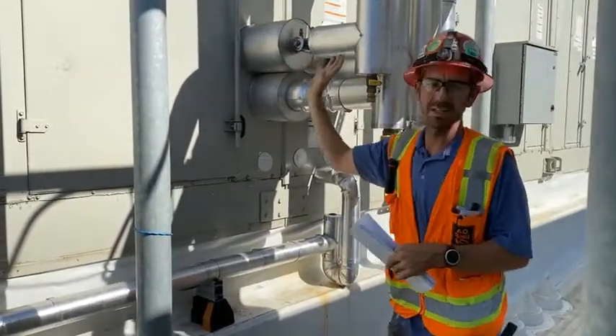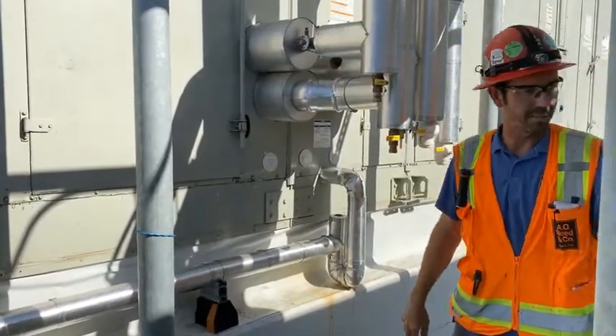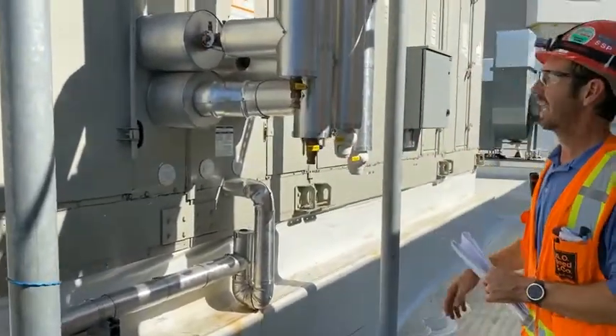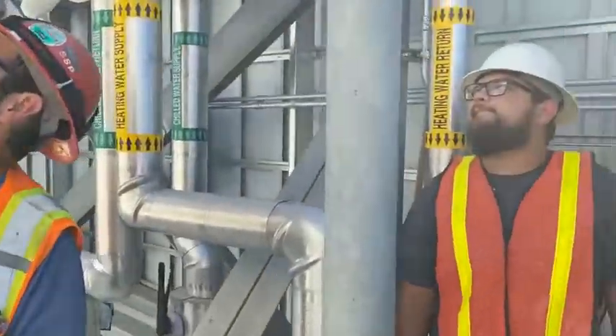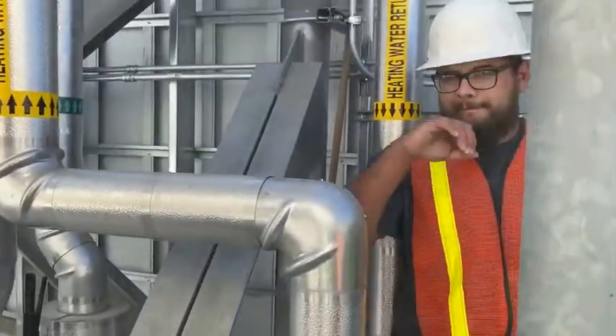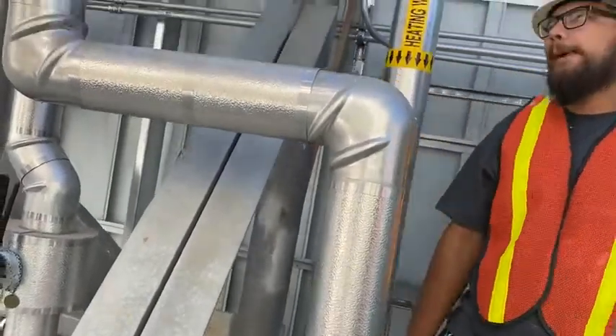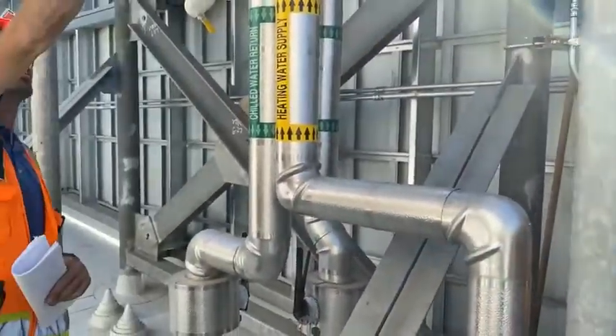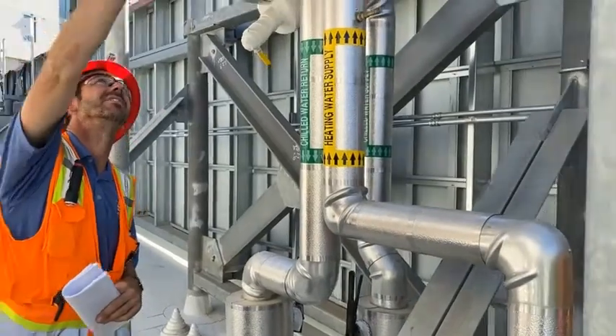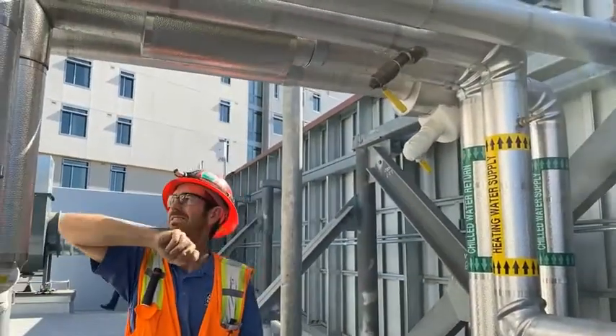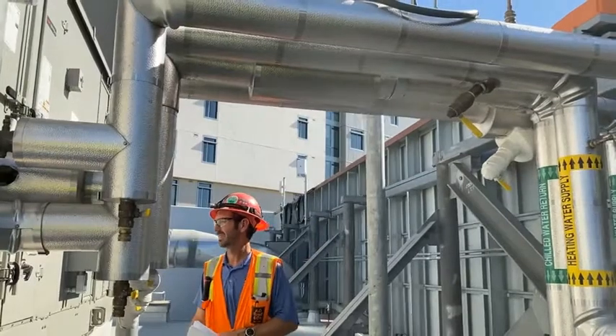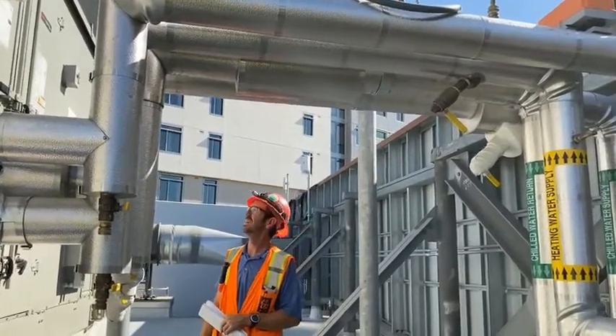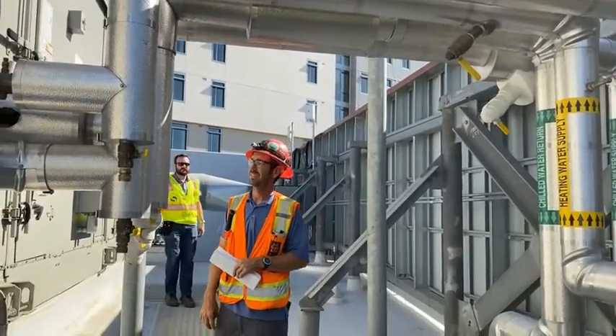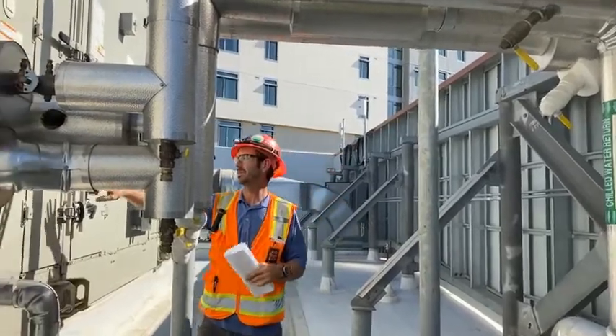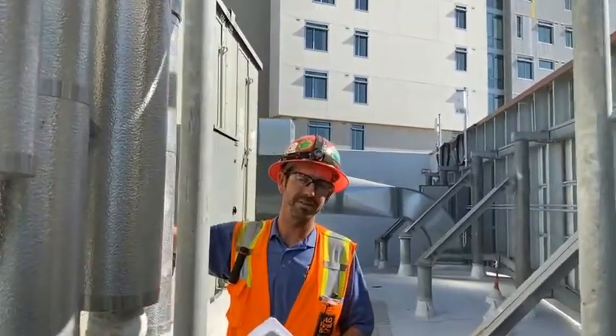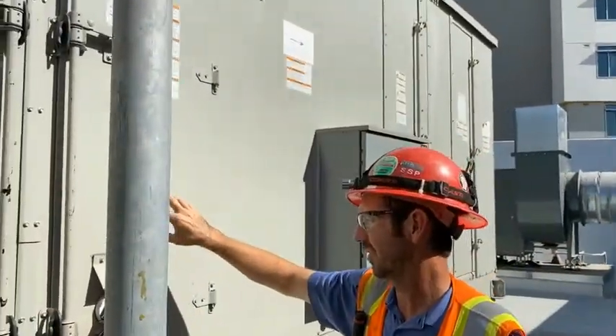So if we're isolating the unit, we'll just do it at the main shutoff valves that are right back behind us. If you do work, use the vents that are up at the top of the piping to vent out any air. Same is true on the chilled water. Strainer on the supply, control valve on the return. Same compartments all the way through. This will be the inlet, the door to the inlet of the fan. This door right here is for the electrical VFD compartment.